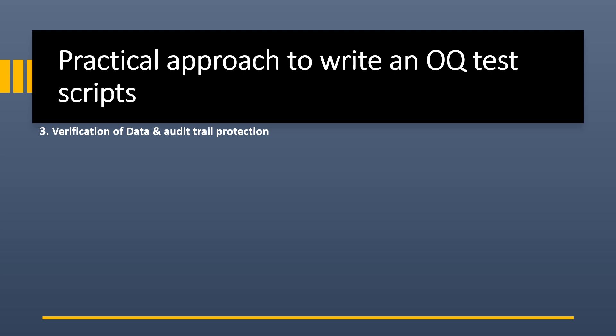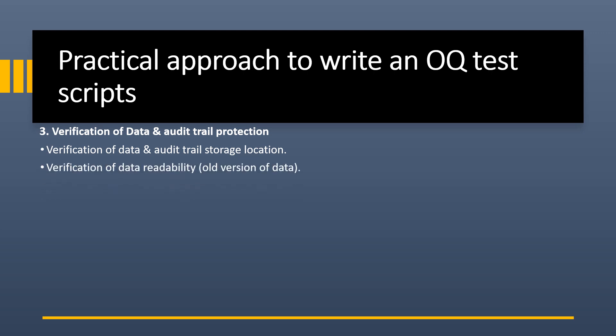Third is verification of data and audit trail protection. This includes verification of data and audit trail storage location — where electronic data and audit trails are saved, whether on a local PC for standalone systems or on a server for server-based systems. Next is verification of data readability — data should be in readable, unambiguous form, and data migrated after a software update should be supported and readable by the new version.